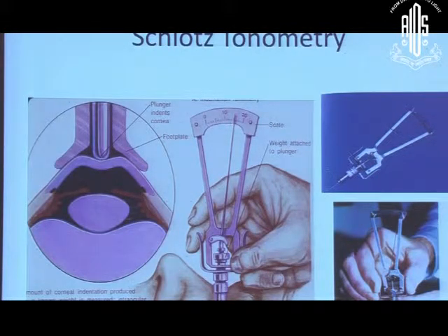If you have to use this, then what I suggest is you do the measurement with the 5.5 weight, which is usually available, and then repeat the measurement with the 7.5 weight added, and take the average of the two pressure readings, and that to some extent is going to nullify the effect of ocular rigidity.